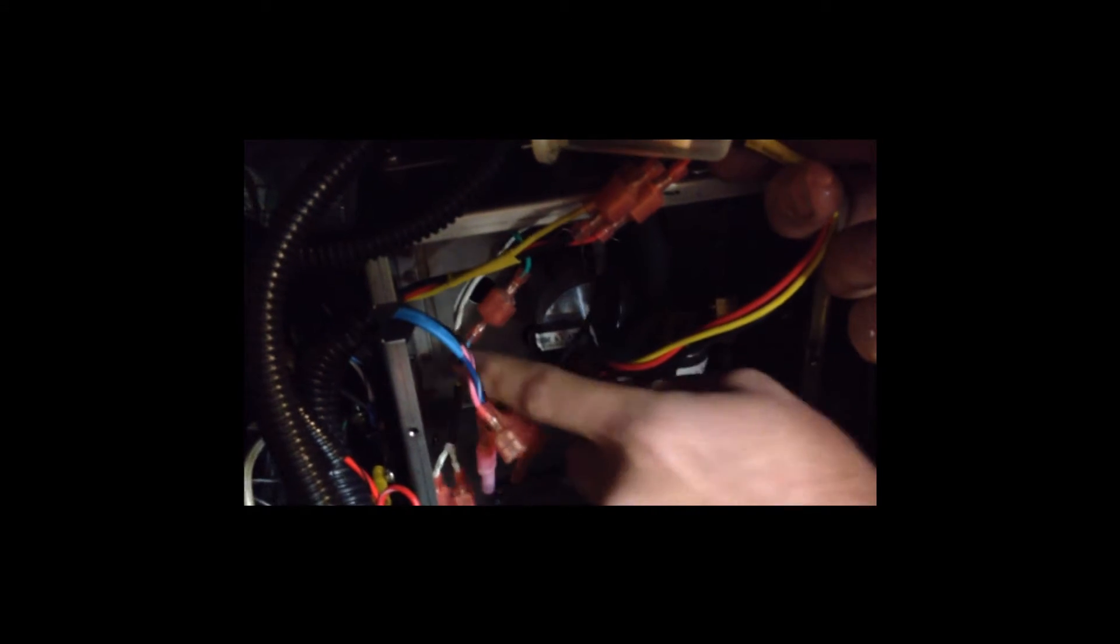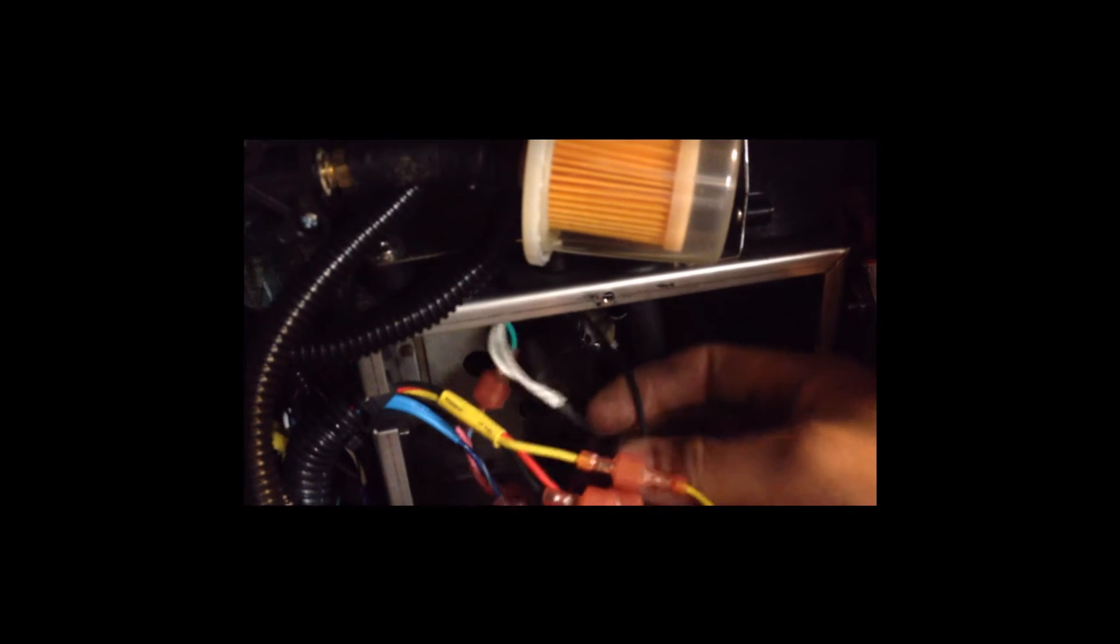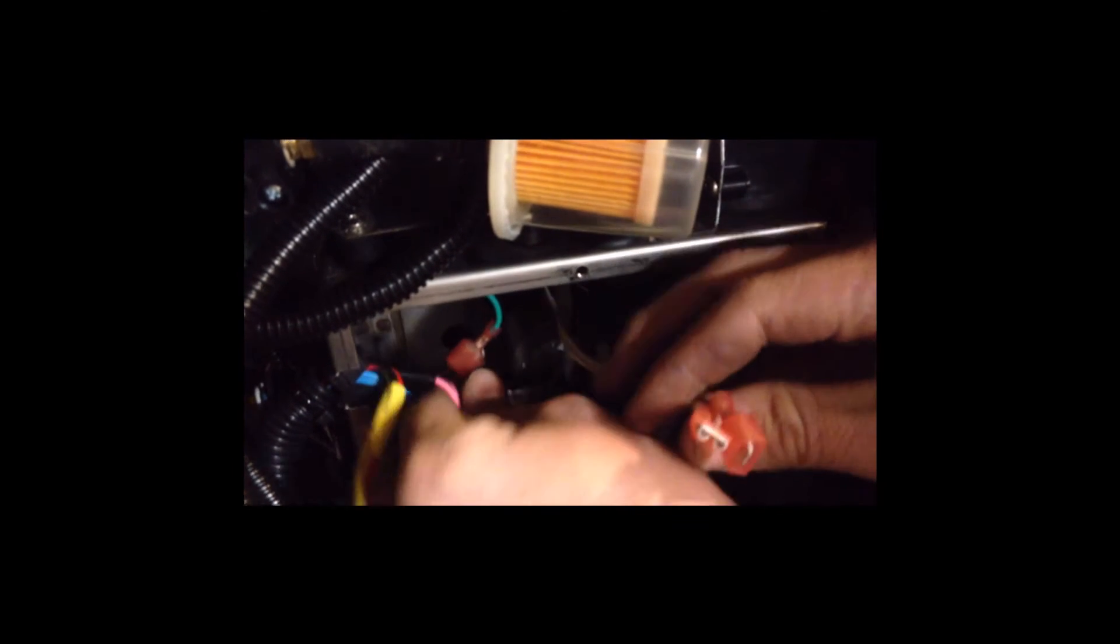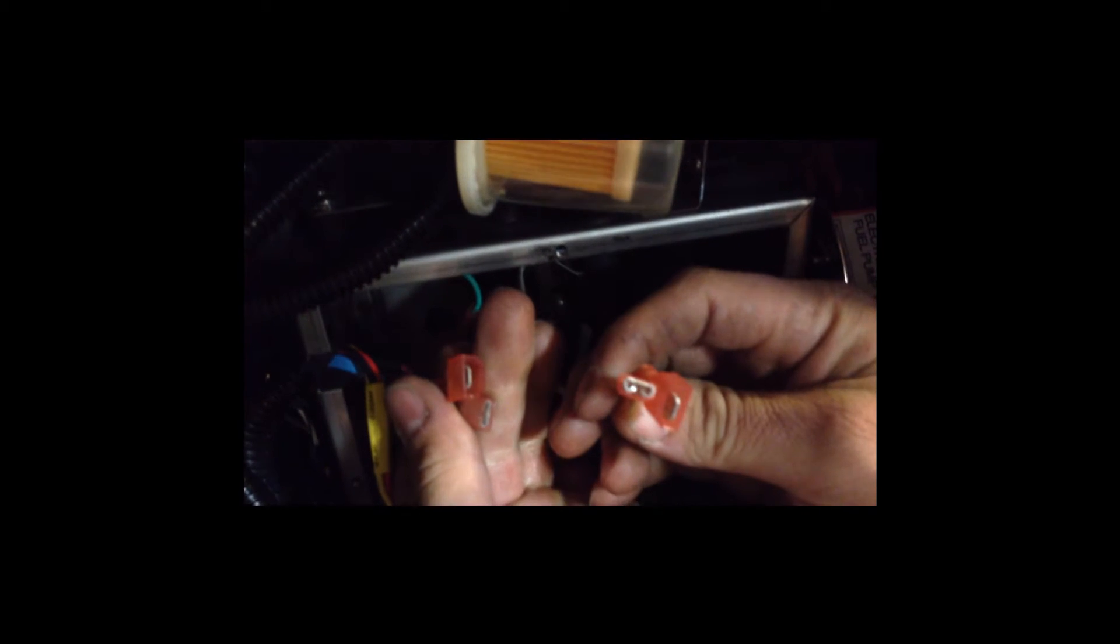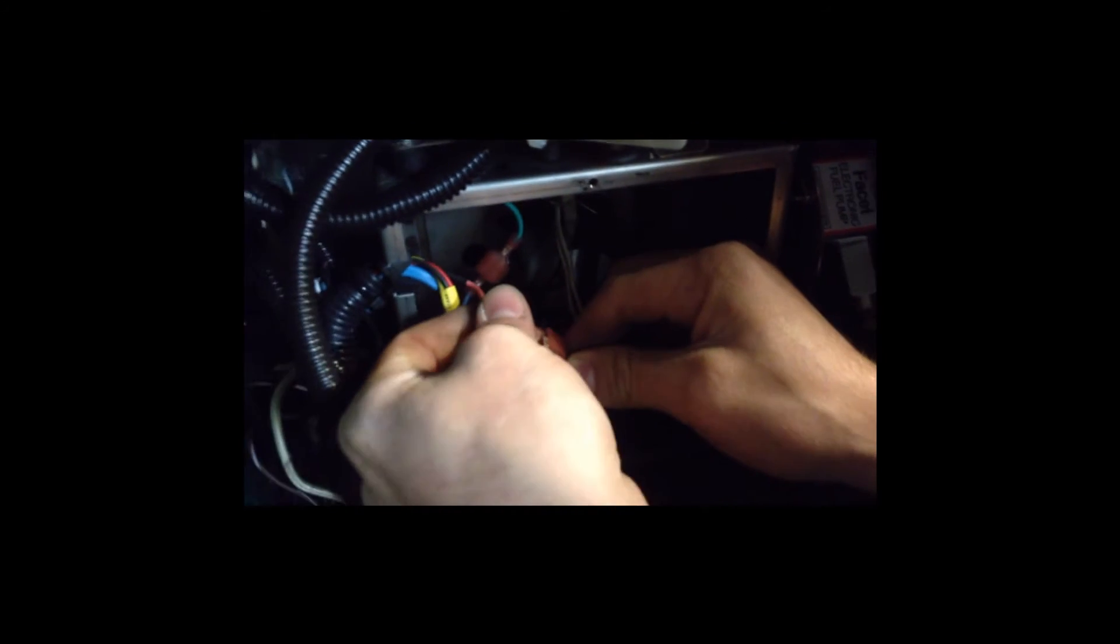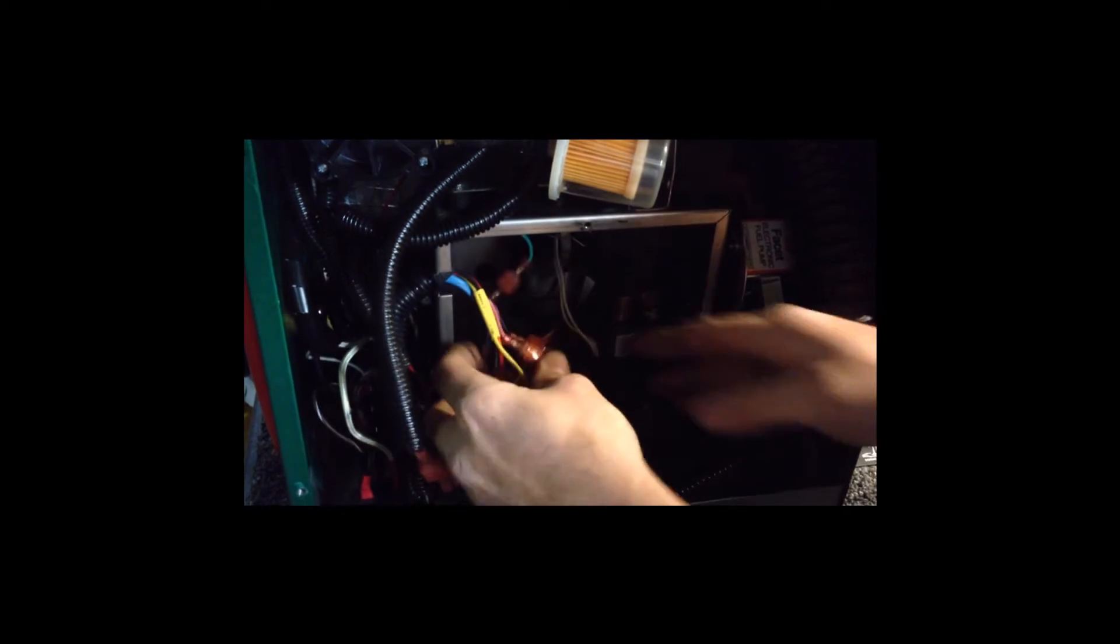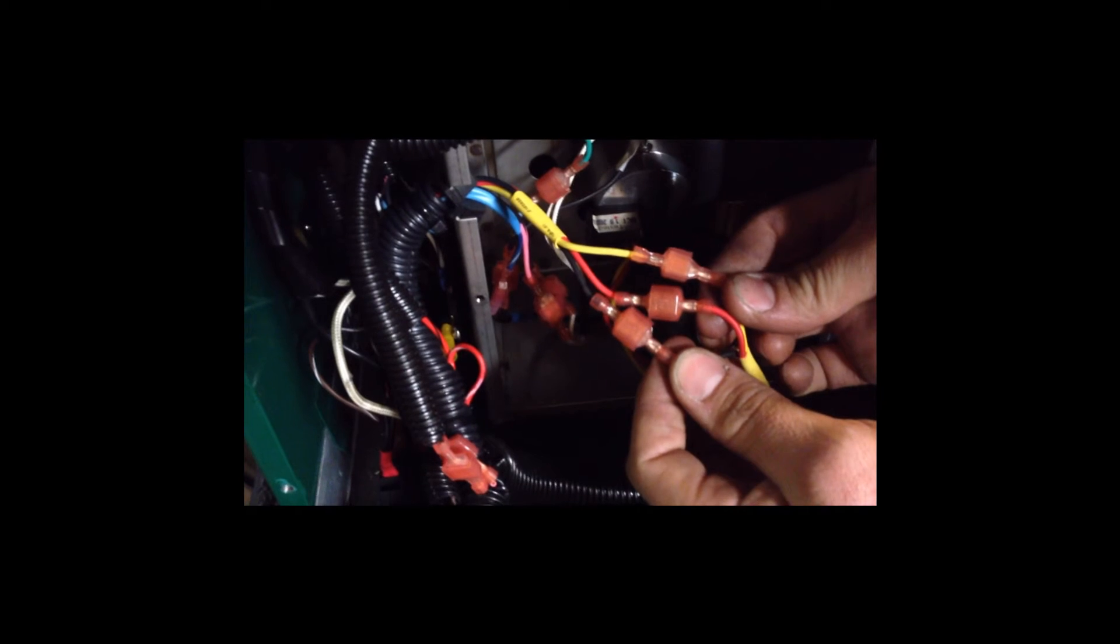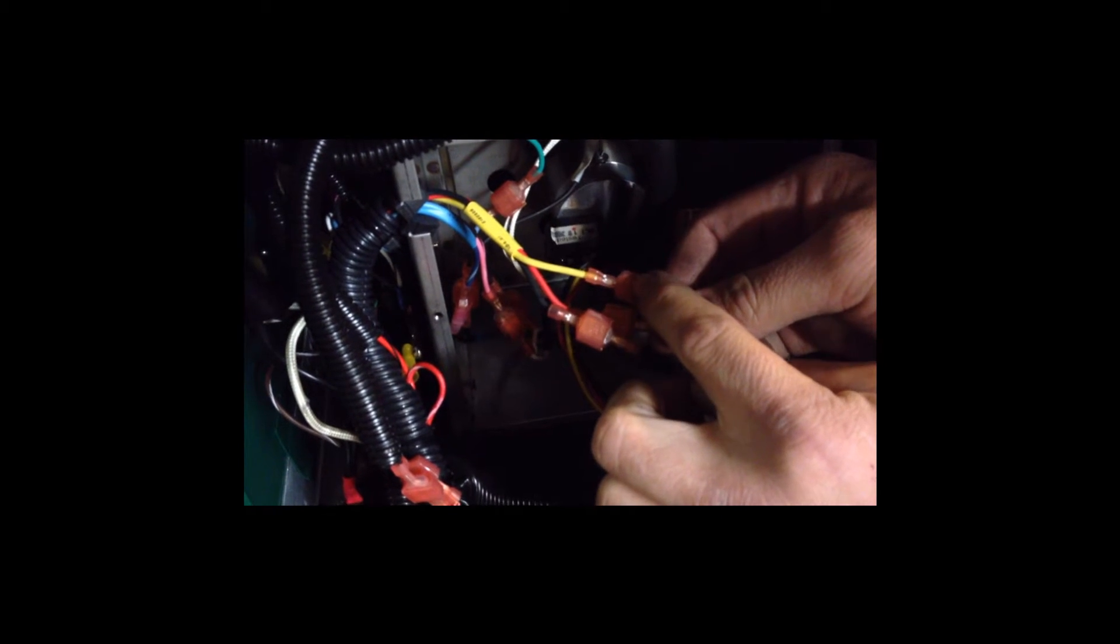Now you have the fuel block in and you can reconnect your igniter wires. One side is male, one side is female. They only go in one way. Now we can install the new flame sensor. The flame sensor is going to have three wires coming off of it. Each one has a different connector, so they'll only be able to go in one way.